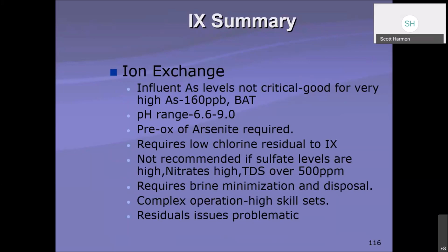In this particular case, pre-oxidation of arsenite is required because you have to change its state for these ions to work correctly. Requires low chlorine residual. Okay, so typically you would not chlorinate this. If your water is chlorinated, you'd have to dechlorinate before it gets into the tanks.